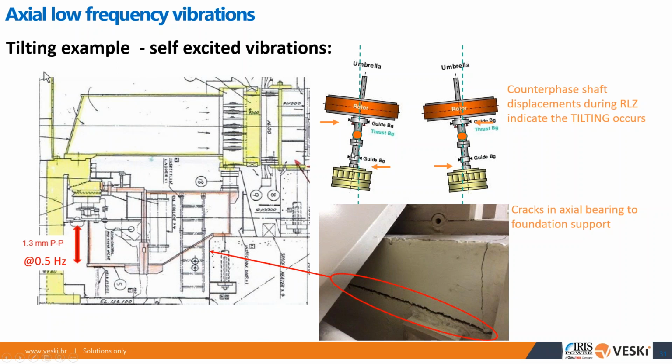It happens because, what we think is, remember that axial thrust, when the rotor lifts and becomes unstable, the oil film breaks, and then the whole structure starts to vibrate on self-excited vibrations. Why does it lift? We still don't know, but it does. This is the fact. And then the tilting also occurs as a phenomenon, which is also a result of that instability.